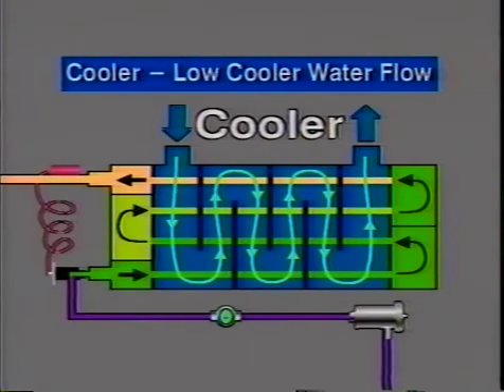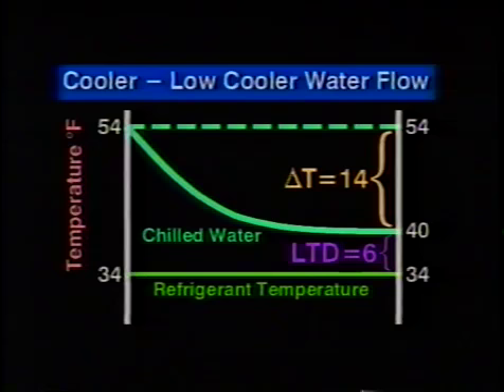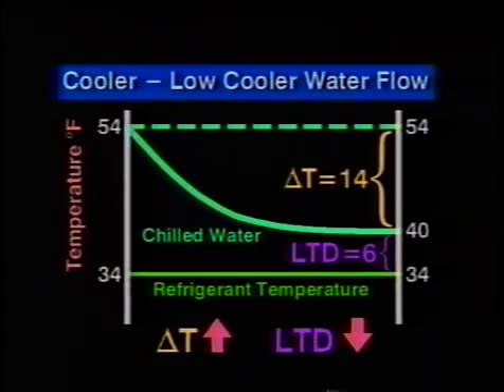Low cooler water flow will cause yet another set of symptoms. In this case, the water is in contact with the tubes longer and so gets colder. But because the flow is reduced, the total system heat transfer is reduced, and the expansion valve will start throttling to try to keep the leaving superheat correct. This means the refrigerant saturated cooler temperature will be lower than normal. Some typical numbers you might see in this situation are return chilled water, 54 degrees Fahrenheit. Leaving chilled water, 40 degrees. Saturated cooler temperature, 34 degrees. Here we see the trend where delta T is higher than design and LTD is lower than design.